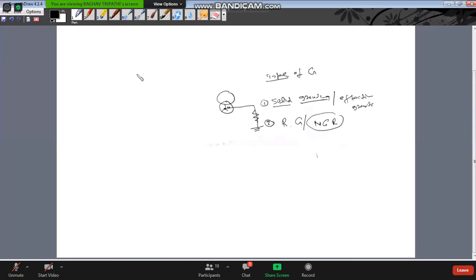Yes, in the case of some substations we also select this NGR. This is utility practice, or when the amount of fault current is higher, in that case, to save the earth pit, we select the NGR. What happens if the whole fault current goes to the earthing? Due to the higher fault current, heat will develop in the conductor, and due to the heat the conductor or the welding joint might get damaged. To avoid that condition, we put in a resistance, and this is called resistive earthing or NGR type earthing. This is the second method of earthing.